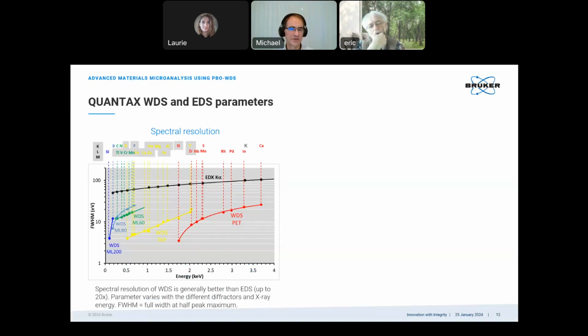One parameter is the spectral resolution, shown here in this graph in terms of the width of the peaks, the full width half maximum, so how broad are the peaks, in respect of the energies analyzed. And we analyzed a lot of different elements, different lines, K lines, L lines, M lines, not shown here. We compare the EDX with the black line. EDX shows peak widths between 40 and 110 electron volts in this range. And WDS shows much narrower peaks. So the half width is much lower.